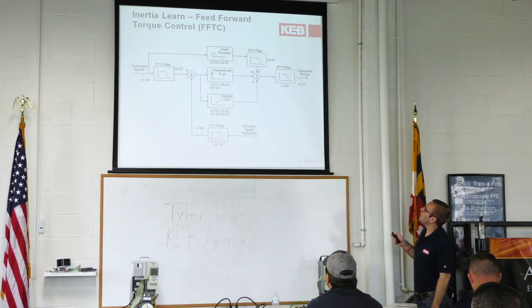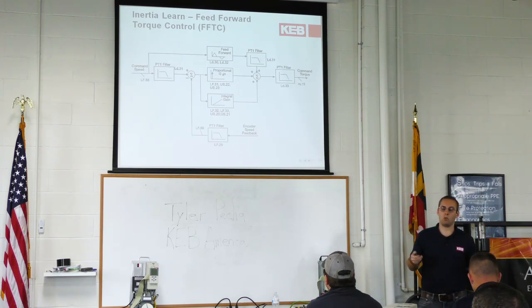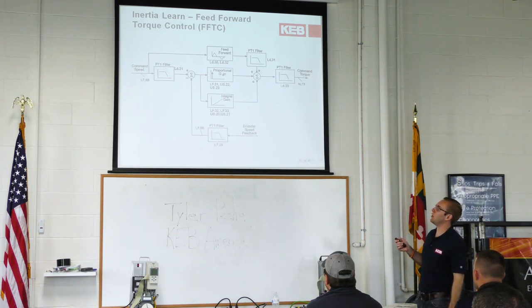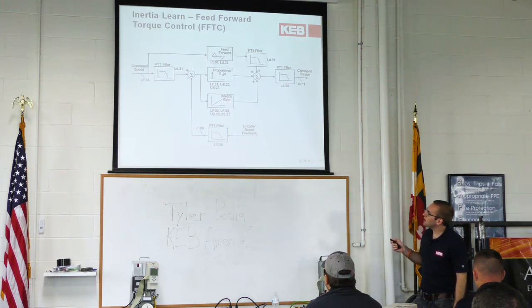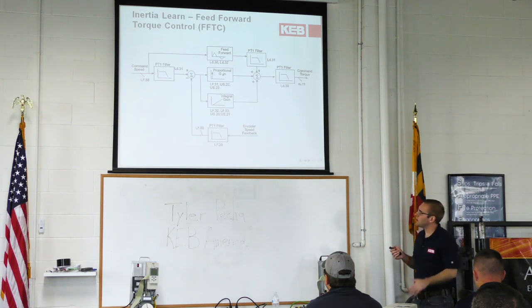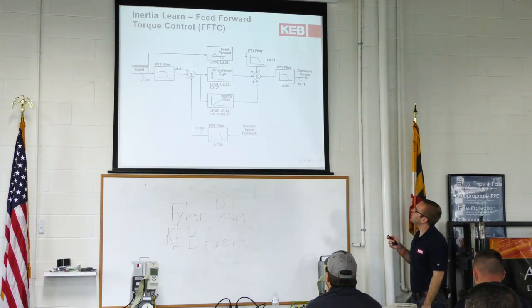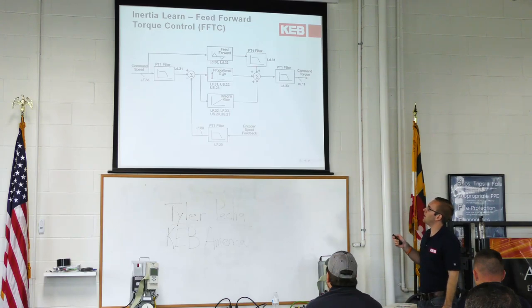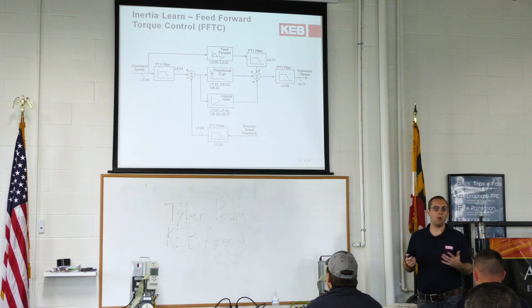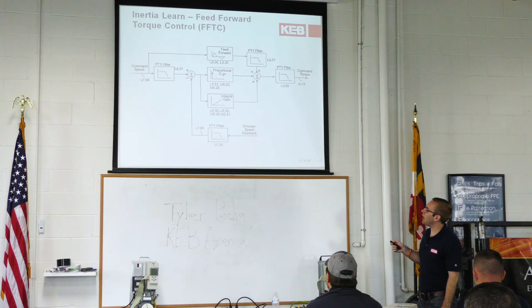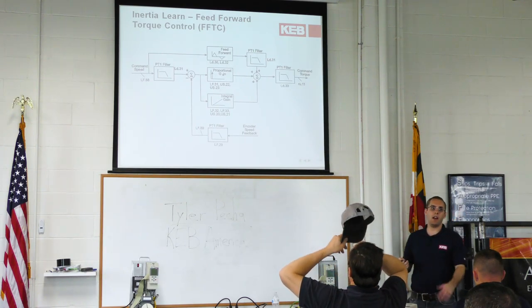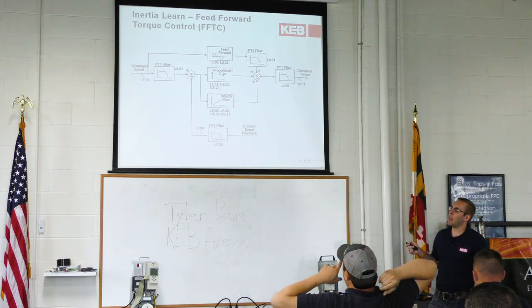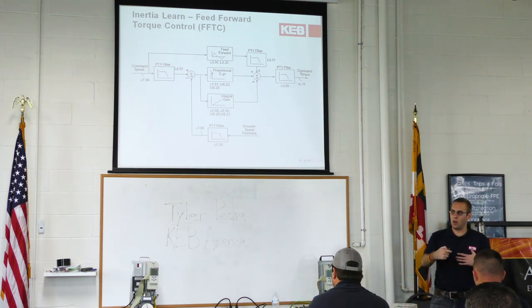The drive tries to compensate, sends out what it thinks it needs, then looks back — now maybe we're at 45 feet per minute, so we only have a 5 ft/min difference. That gets thrown back into the loop, and that's where the integral gain starts to come in because more time is involved, helping you settle in. This loop is happening constantly on a microsecond level. Without feedforward active, you're strictly relying on feedback from the encoder, and your response is only as good as that feedback — there are delays because nothing is instant.